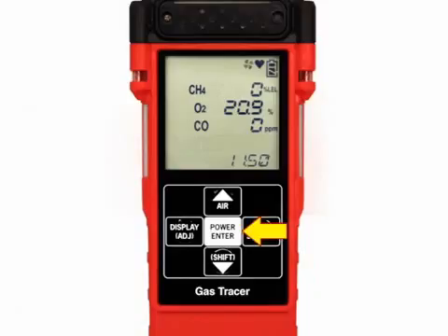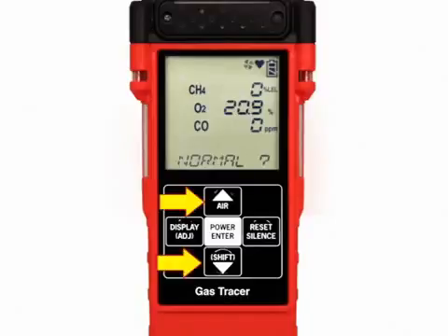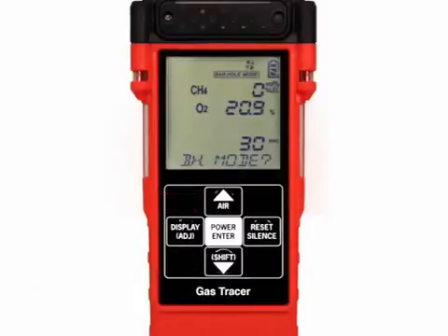Press and briefly hold down the power enter button. The normal mode select screen displays. Use the air or shift buttons to scroll to the bar hole mode select screen. This screen will only appear if the LB mode setting in maintenance mode is set to BH. Press and release the power enter button to begin the bar hole mode startup sequence. If no button is pressed for 20 seconds, the unit will proceed into whichever mode is displayed.